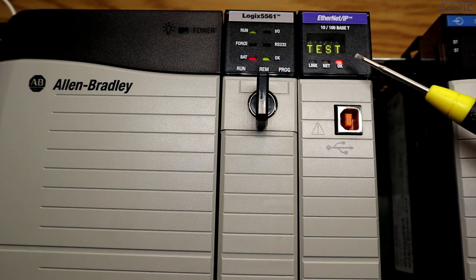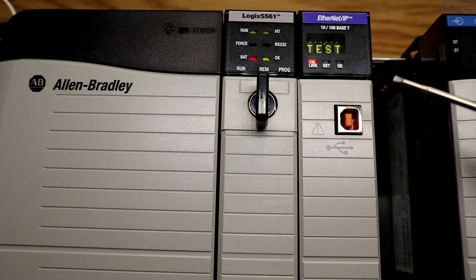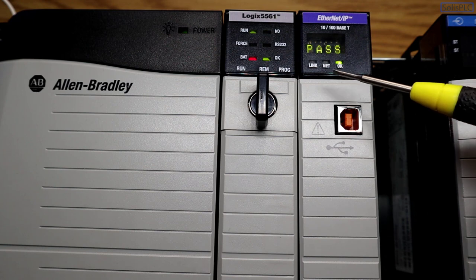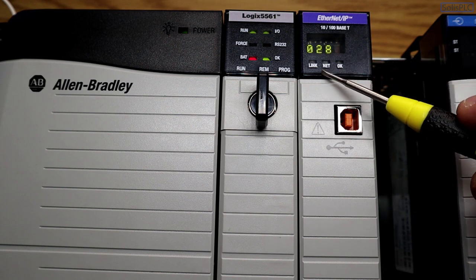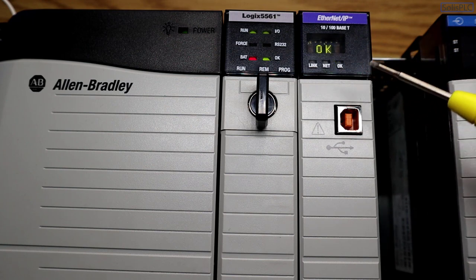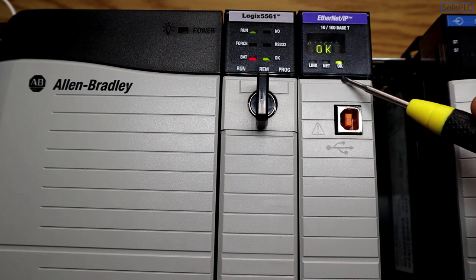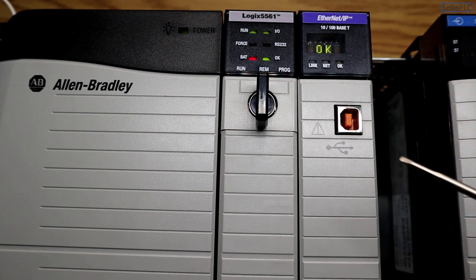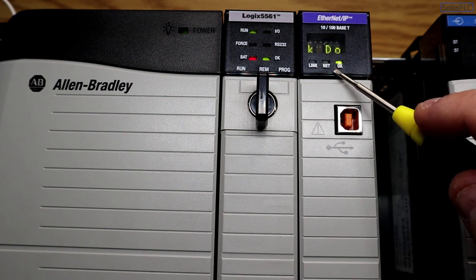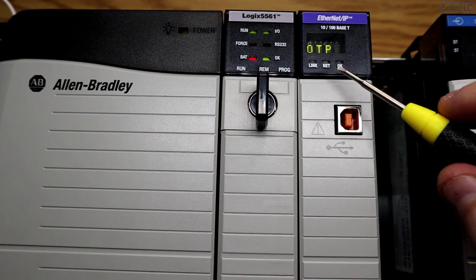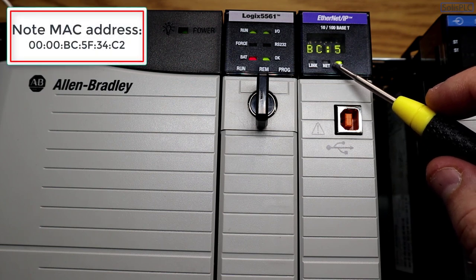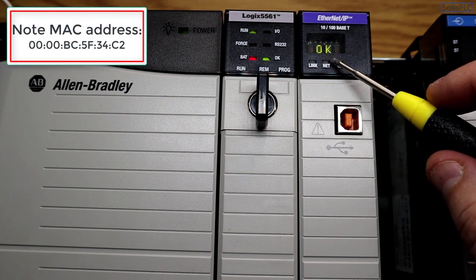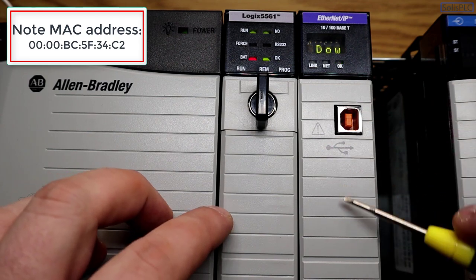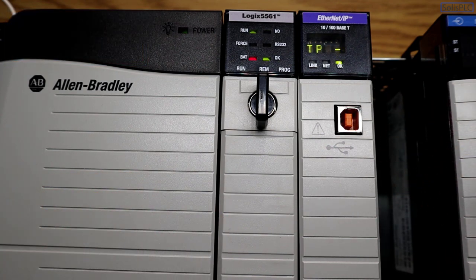So the card is going through a test. This is the normal startup sequence and we should be able to pass. And then it should display the MAC address of the card. So revision 5.028. Everything looks good, so there's no longer the red light flashing that we had prior to setting the switches to three zeros. So link down, which is good. Boot P, as you can see, is enabled and it's showing the MAC address. That way you can write this down or essentially memorize it. And if you have only a single device, then it should be the only device that's going to come up on boot P.